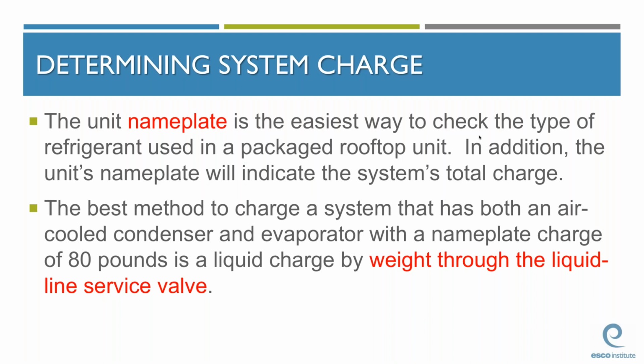When the system's charge is known, it's always best to charge the system by weight. Of course, liquid charging through the liquid line service valve is much faster than vapor charging, especially when the system holds a lot of refrigerant. One thing I like to do is ask my students which method of charging is faster, liquid or vapor, and that just helps to stimulate some classroom discussion as you work your way through this content.